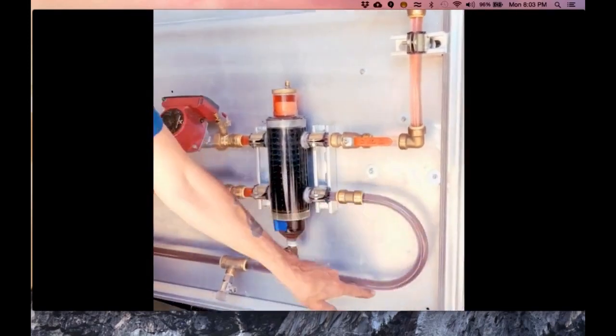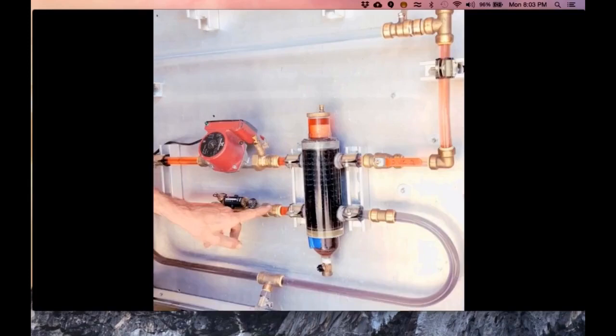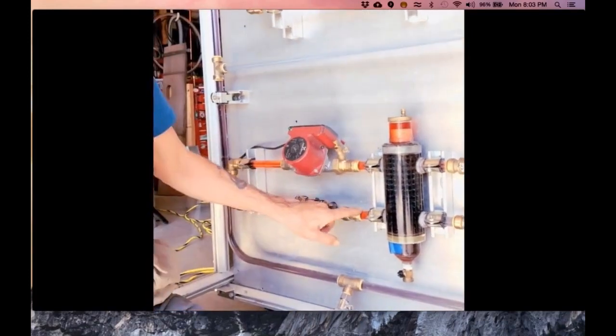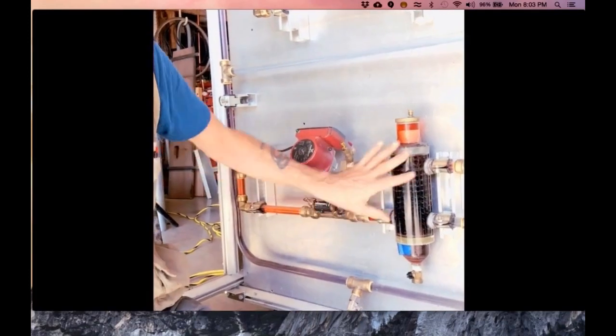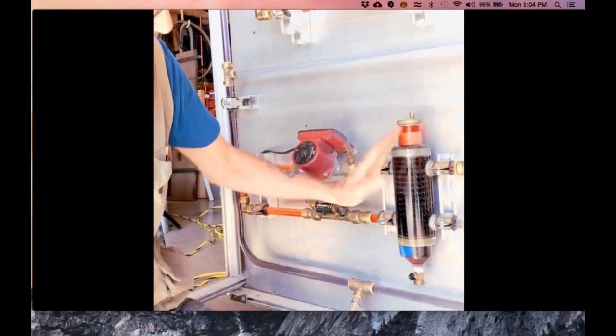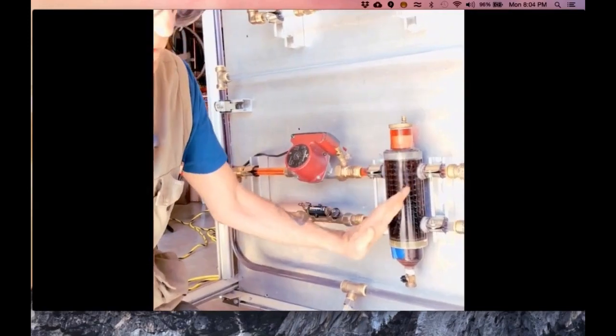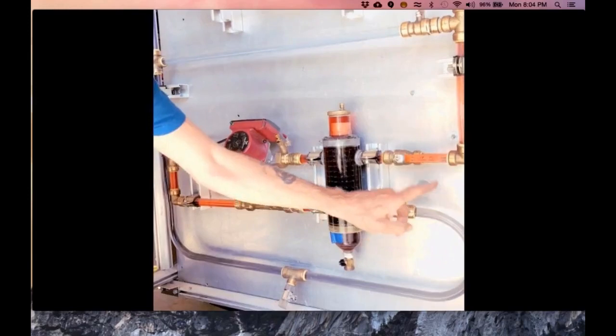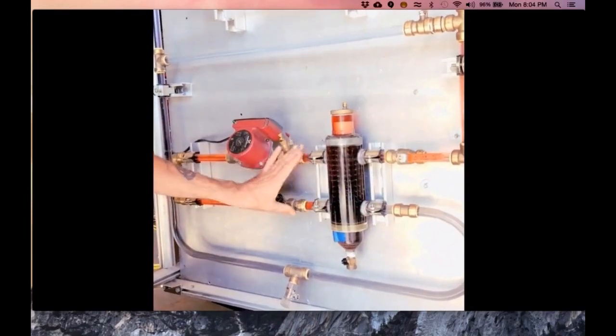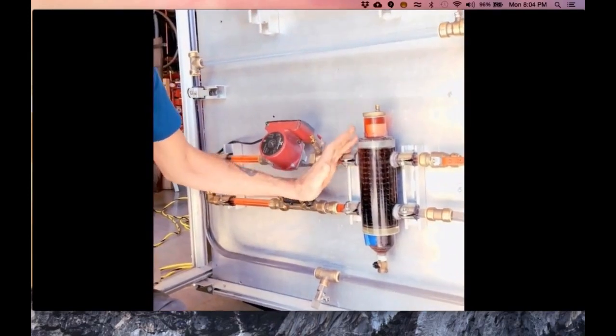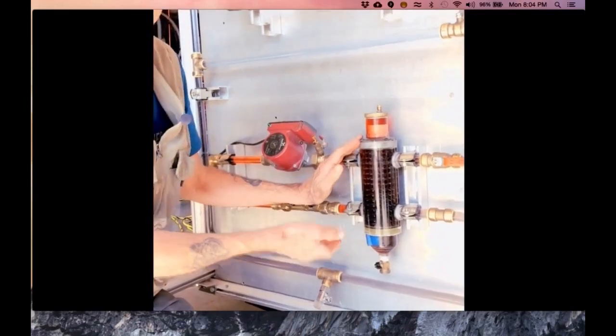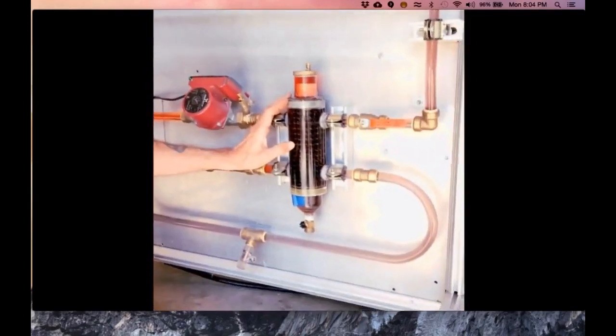So now I've got flow going around through here, through the primary loop. Notice how this is staying red. I'm not getting any purple over here because this is actually separating, even though it's all the same water, all in the same tube. This big chamber in the center becomes my separation device, and that's how I can get the one color going through here, no effect to the color going over here. So next, I'm going to shut it off, and we're going to take the magnet off. We're going to blow it down. I'll show all the particles that we just put in up on top a minute ago and see how the third magnetic separation part of this works.